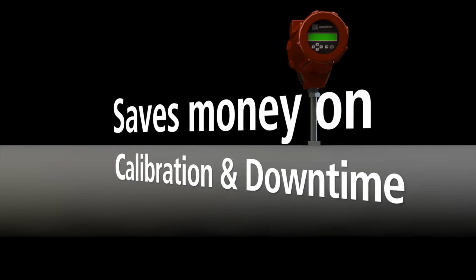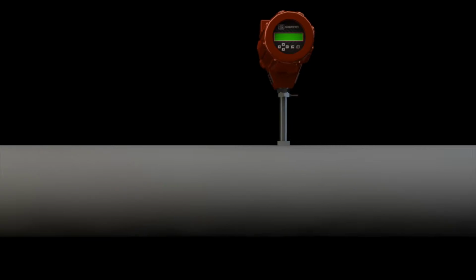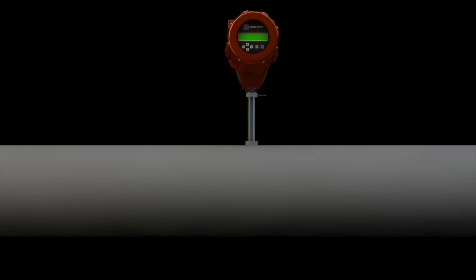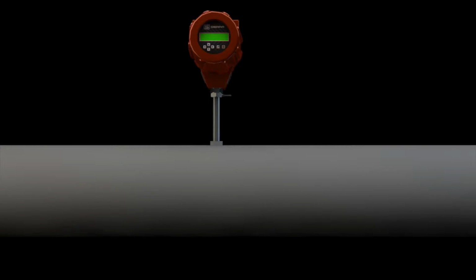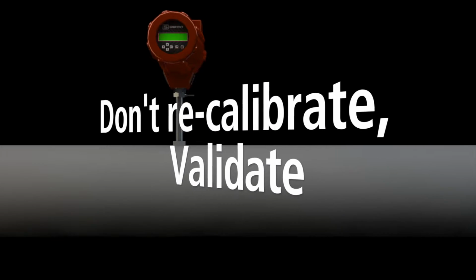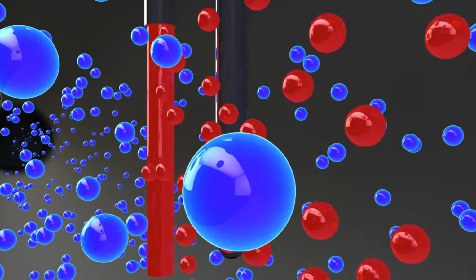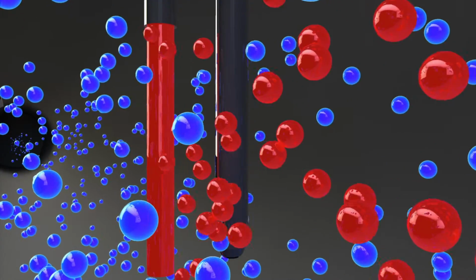In-situ or field calibration validation of thermal meters is a highly marketed feature because it saves money on calibration and downtime. Sierra customers have enjoyed this advantage for many years. Sierra's motto has always been, "Don't recalibrate, validate." But be careful, there is a lot more going on behind this statement than you may first think. There is a lot of smoke and mirrors by thermal manufacturers about in-situ calibration.